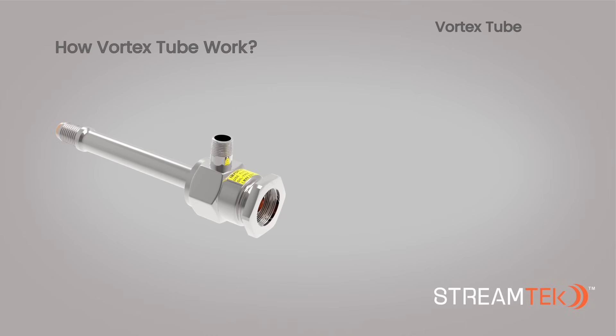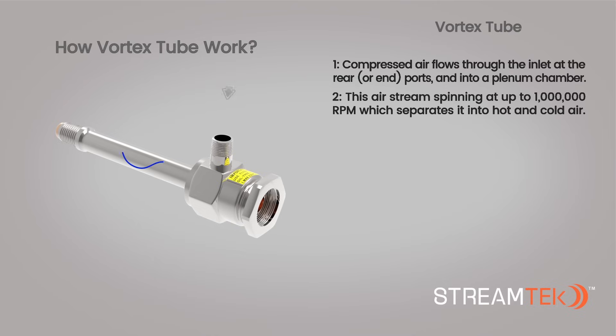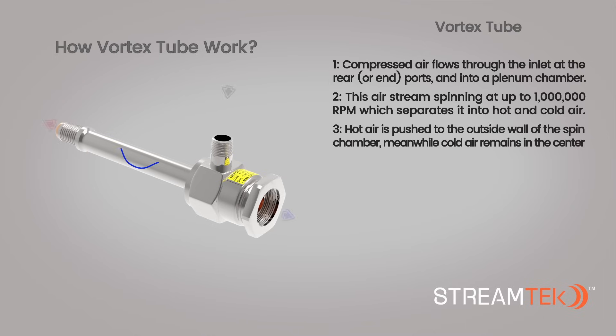How does the StreamTek Vortex Tube work? 1. Compressed air enters the Vortex Tube at a standard NPT inlet port and travels through the Vortex generator into the spin chamber. 2. Inside the spin chamber, the air stream spins at up to 1 million revolutions per minute, which separates it into hot and cold air.